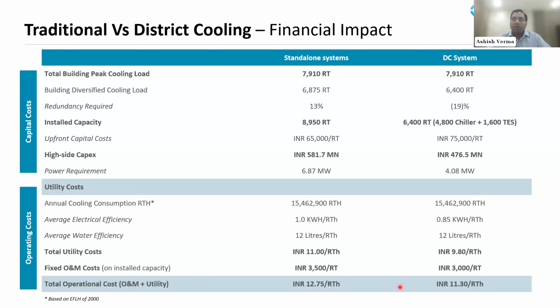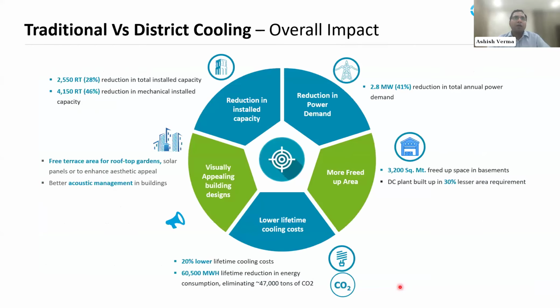So when we compute the utility cost basis above equipment selections, we are arriving at a number of 11.3 rupees per RTH for a DC system versus 12.75 rupees per RTH for a standalone cooling system, which demonstrates the saving as far as operation is concerned for a district cooling plant. This is the overall impact. This is just, again, the same thing. There is a reduction in installed capacity, reduction in power demand, more free area for the developer or the end user, lower lifetime cooling cost, and visually appealing buildings.